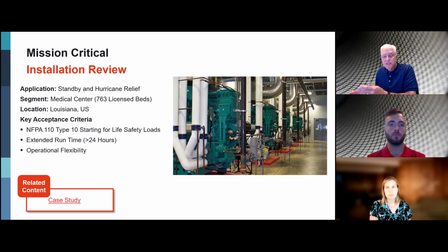First, it's an unlimited supply of fuel the hospital can use until normal power is stable and returned to the grid. During catastrophic events, this could be weeks, as you know. Secondly, it's a cleaner burn, more environmentally friendly in carbon emissions. Third, there are additional cost advantages in implementing natural gas units, as the hospital can now take advantage of peak shaving exercises with the local utility.